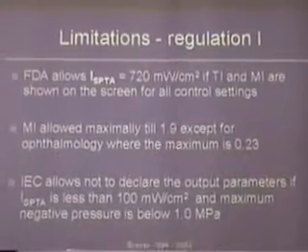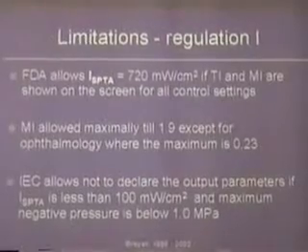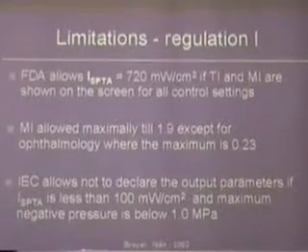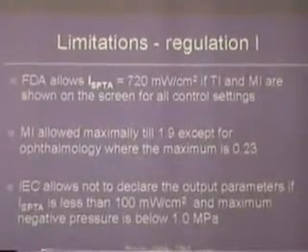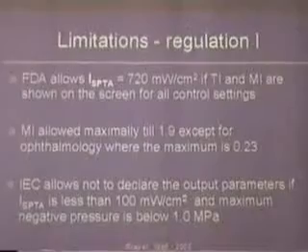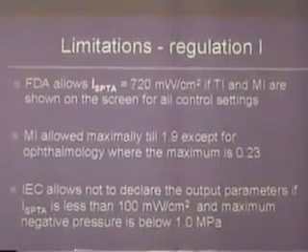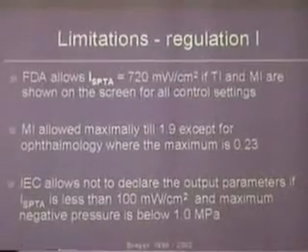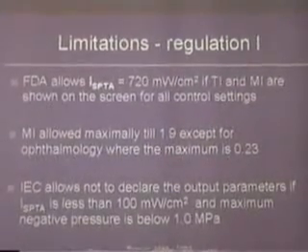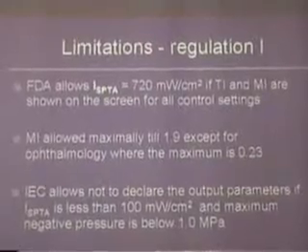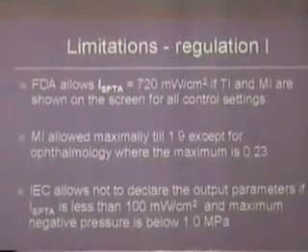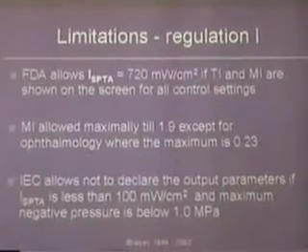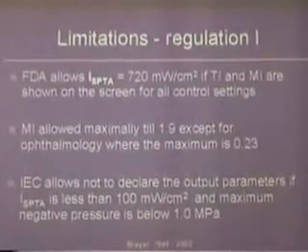Ophthalmology is an exception for many things, and that includes the mechanical index. But if our machine, whatever ultrasound, can transmit less than 100 milliwatts per square centimeter, then you don't need to have any label. And that's the fetal heart detectors. They will typically have much less than that, and they simply don't have any label because they are in a safe region by themselves. Next, please.